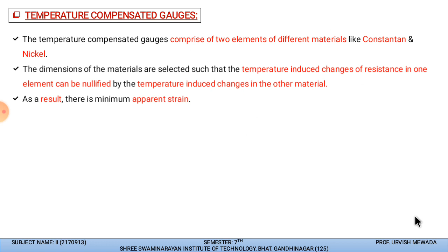So whenever the temperature increases, the dummy gauge will nullify the temperature increment, and the temperature-induced change in the other material can be nullified with the help of a dummy gauge, or we can say a temperature compensated gauge. So as a result, the minimum apparent strain will occur, and the strain gauge can show the accurate reading. So temperature compensation through the bridge arrangement, this is how we can compensate the temperature.